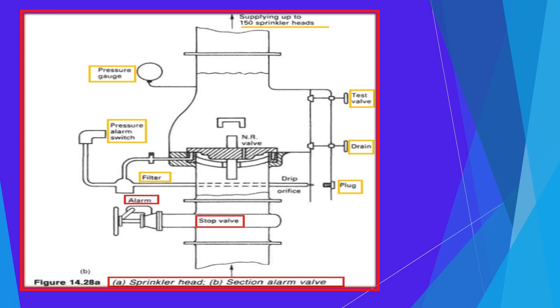Okay, as we have seen in the previous slide how the non-return valve operates, in this one we are going to see the actual functioning. First of all, I am going to tell you about the description of the parts which you can see. This is the non-return valve, and this is basically the valve blade. This is the stop valve, which is locked open, and on this side your sprinkler heads are being attached. Here it is written 150, but as per the regulation now it is 200, the maximum number of heads that can be installed.